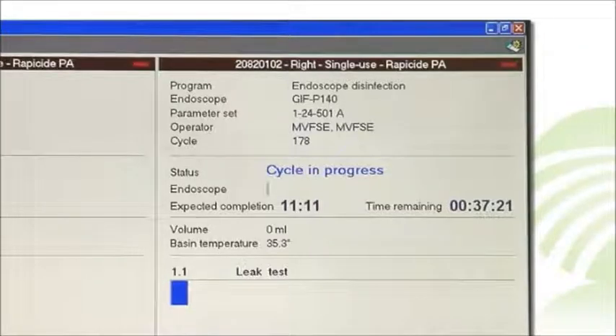The first operation is monitoring of system sensors. Next, the leak test is activated and continues throughout the entire reprocessing cycle. The endoscope is pressurized and the pressure is monitored for a period of time. If the pressure drops below a set reading, a leak has been detected and the process is halted. The phase following the leak test monitors channel connectivity and blockages.